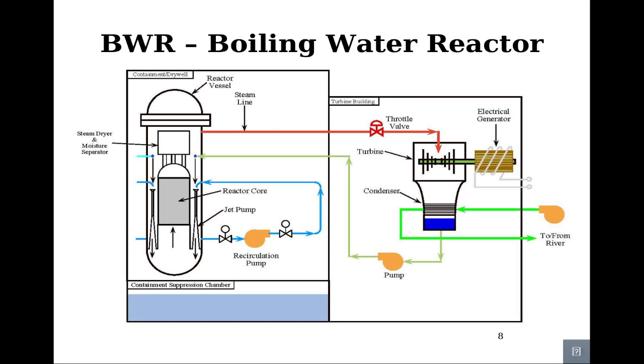Here we see the simplified drawing of a boiling water reactor. It uses demineralized water as coolant and neutron moderator. Heat is produced by nuclear fission in the reactor core, and this causes the cooling water to boil, producing steam. The steam is directly used to drive a turbine, after which it is cooled in the condenser and converted back to liquid water. This water is then returned to the reactor core, completing the loop. The cooling water is maintained at about 1000 psig, so that it boils in the core at about 550 degrees Fahrenheit.